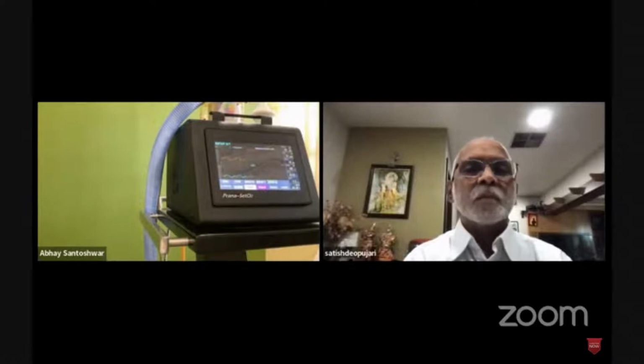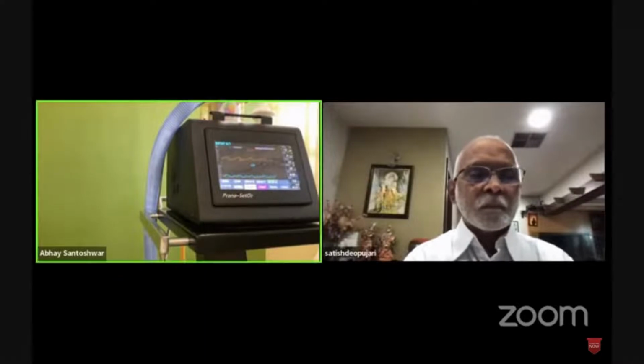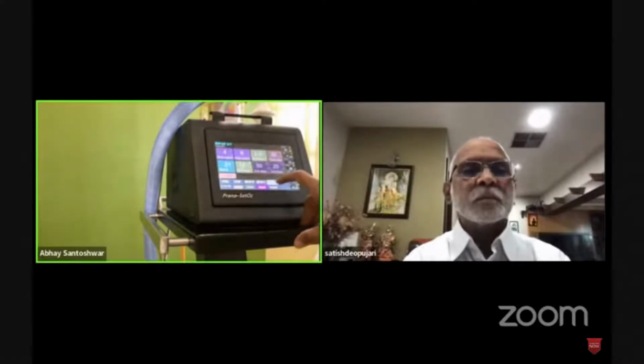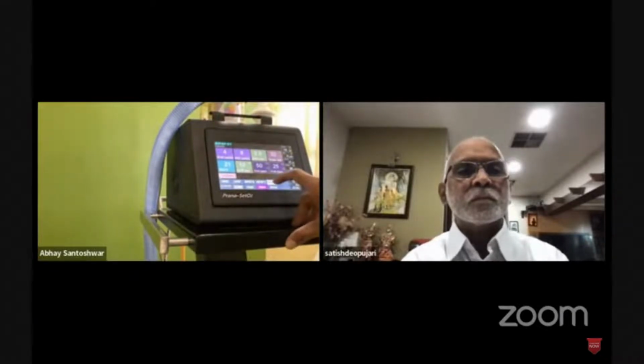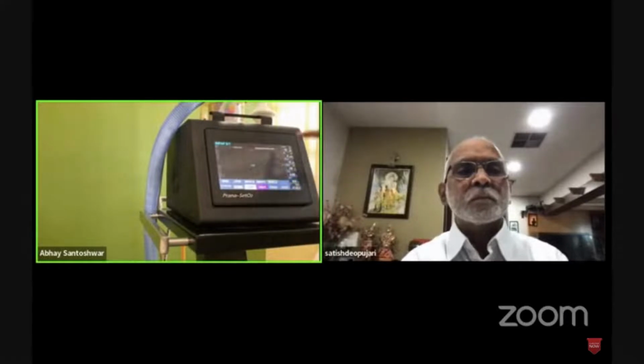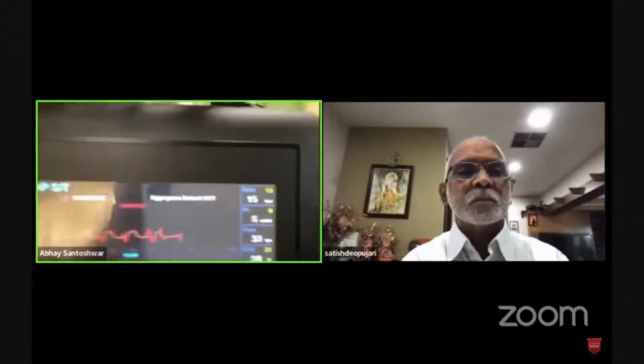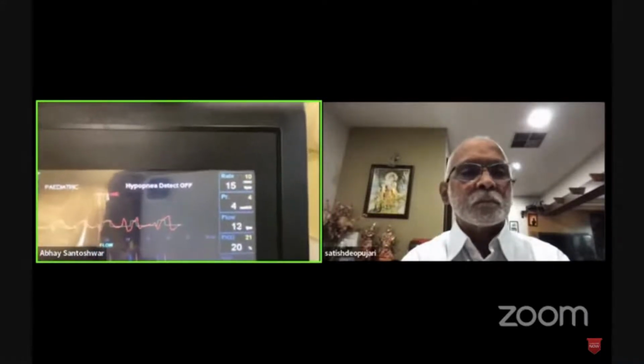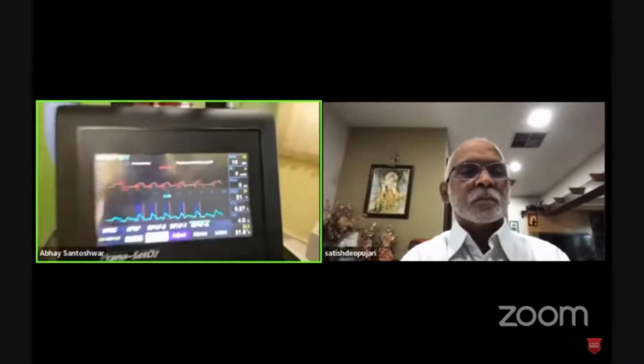In this last one which has been shown, I wanted to ask, what was the mandatory breath and what was the triggered? The color of the graph. Fine. So the set rate that was there was 10. And now if you see, if the patient is triggering, you are able to see 10 here on the window. And when the patient triggers, there is an averaging method used so that you don't have false triggers being noted. I have taken 3 triggers in a row and you see the rate changing. So if you see here on the window, 10 was the set rate and 15 is the rate at which he is right now breathing.